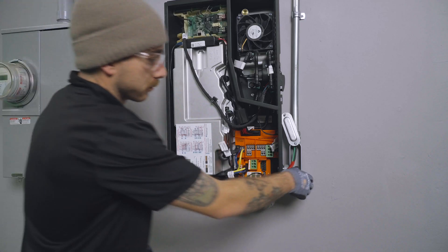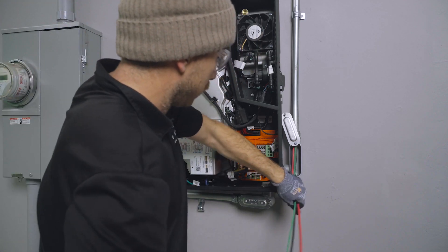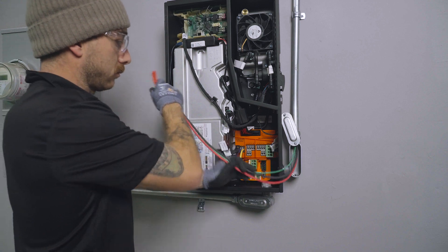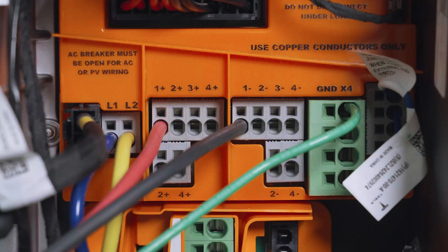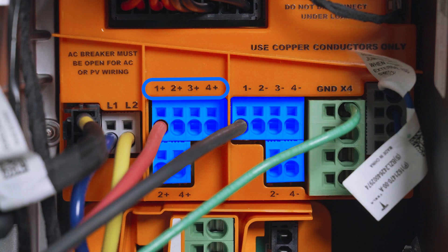Begin by terminating the conductors for the DC conduit into the solar inverter. Start by terminating the equipment grounding conductor in an open ground terminal. The remaining positive and negative conductors will be connected to these terminals, labeled positive 1 through 4 and negative 1 through 4.